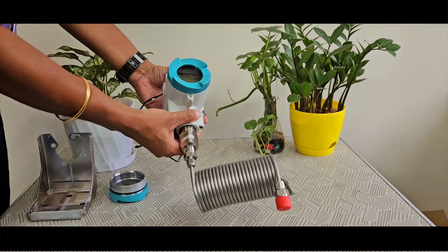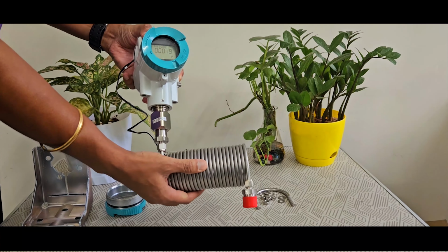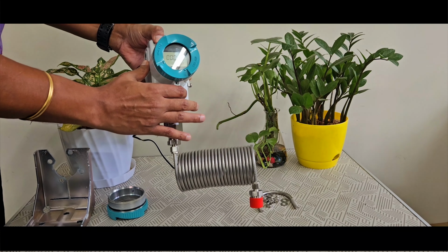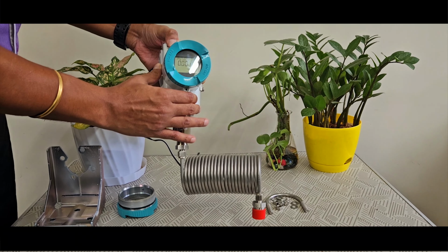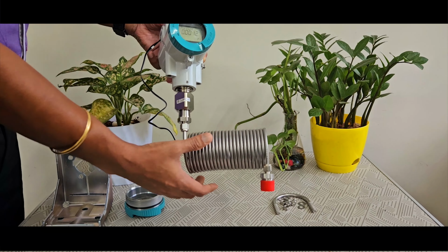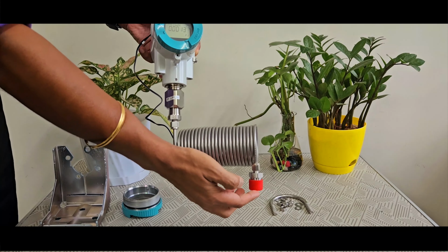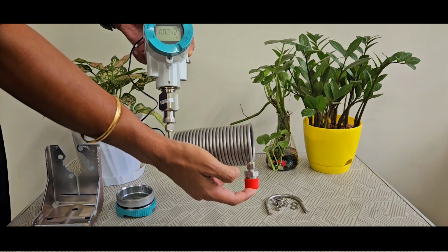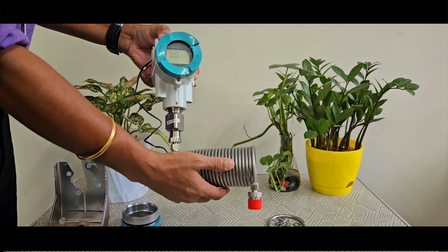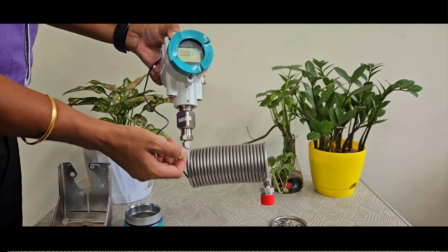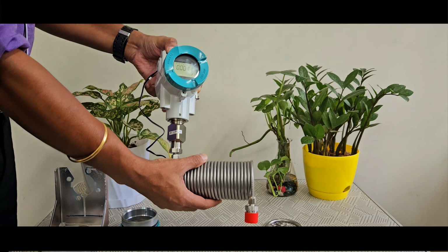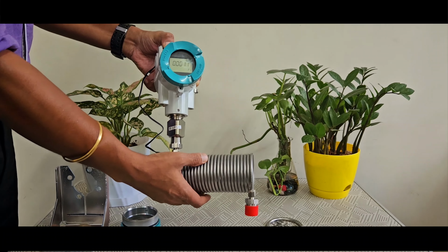So in some scenarios what happens is that the line temperature would be higher and the temperature which this particular pressure transmitter can take will be lower. So in these cases we use the cooling coil. So this is the cooling coil which is fixed along with this pressure transmitter, where one side is for the process, which means that at this point the temperature would be more than 400, 500, 600 degrees, which has to be further reduced to 150 degrees, which this particular pressure transmitter can take. Hence these cooling coils are used, or we can use the siphons also to reduce the temperature.